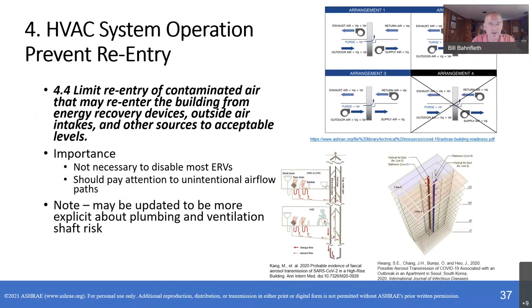With respect to reentry of contaminants, our recommendation is to limit reentry from energy devices and outdoor air intakes and others to acceptable levels. Initially, the recommendation for many sources was to disable ERVs. And thinking about that more deeply, we found that most ERVs can probably operate safely and have put guidance in place for that. We also need to pay attention to unintentional airflow paths, because we have seen evidence that plumbing systems and natural ventilation shafts can be sources of reentry as well.